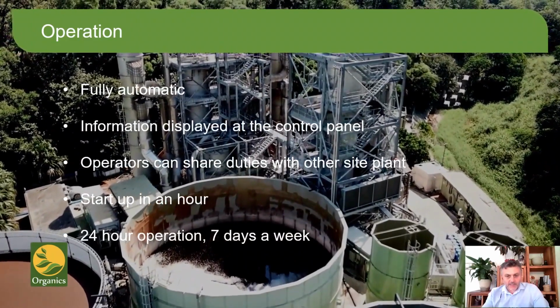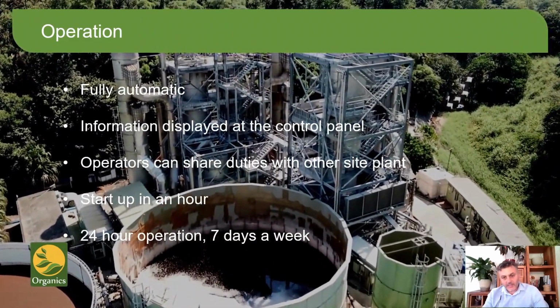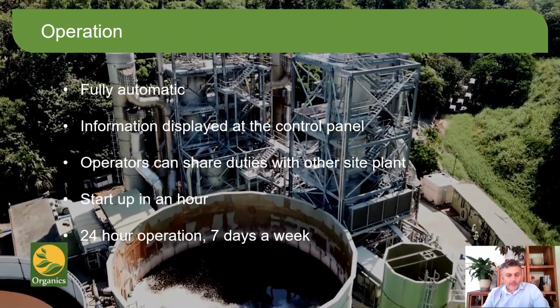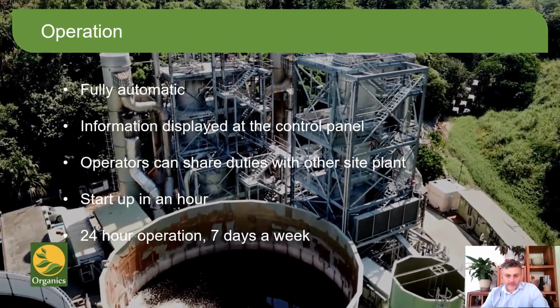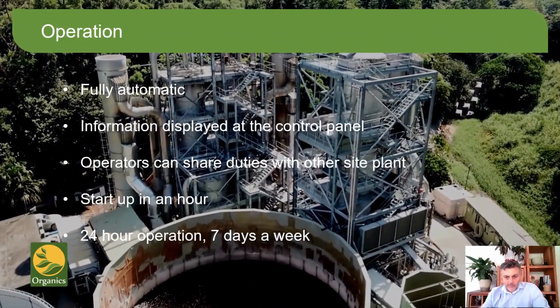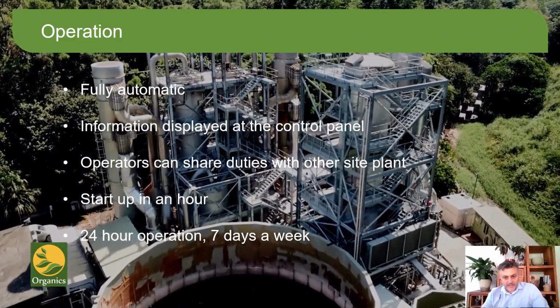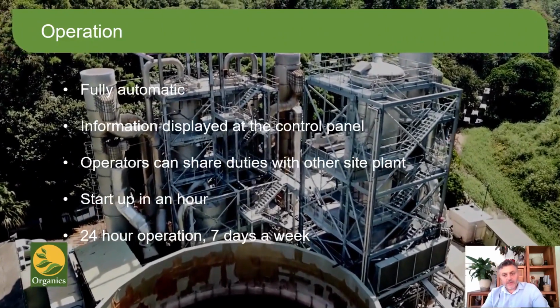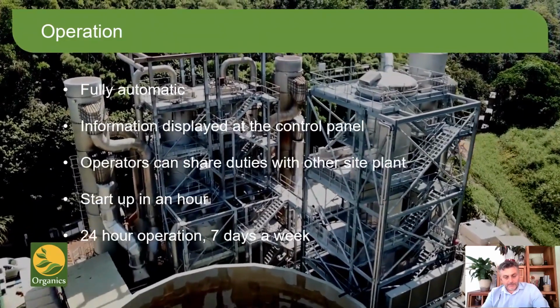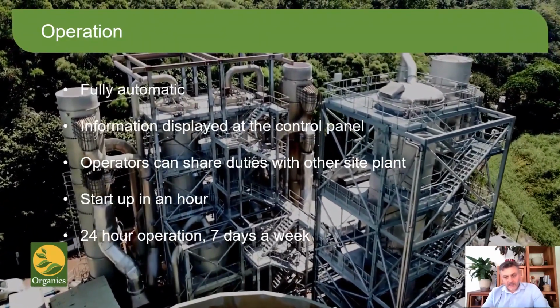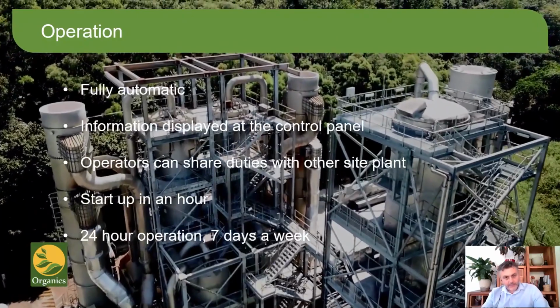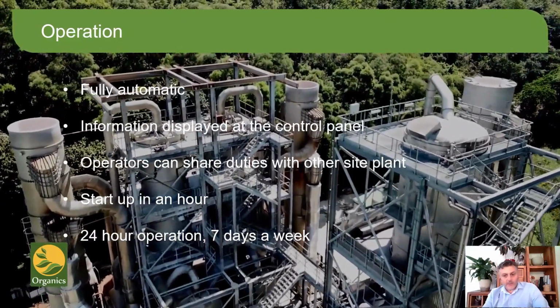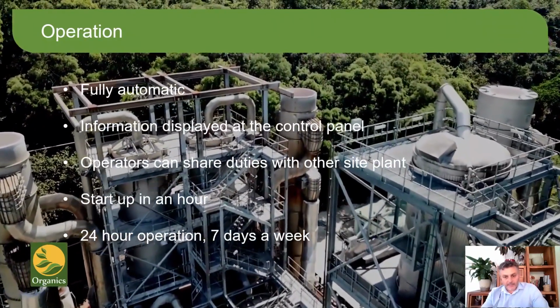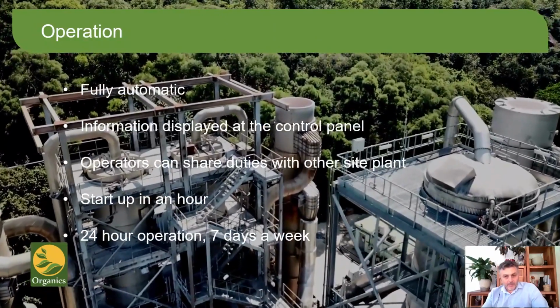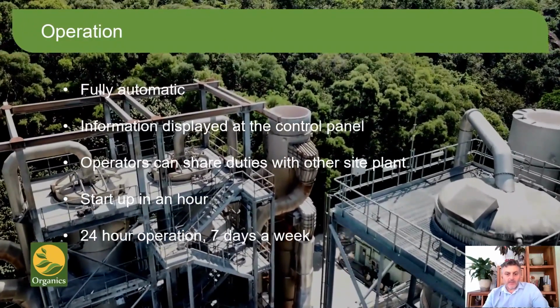The system uses an HMI display to show the system information and to allow the operator to make adjustments to flow rates, etc. The operator will typically share other site duties, and any competent operator could be trained to run the system in a day or two. As I mentioned earlier, the startup time is quick, usually taking less than an hour, and the system typically then runs 24 hours a day for weeks at a time. By monitoring heat exchange and stripping performance, the service interval can be established and varies from site to site.